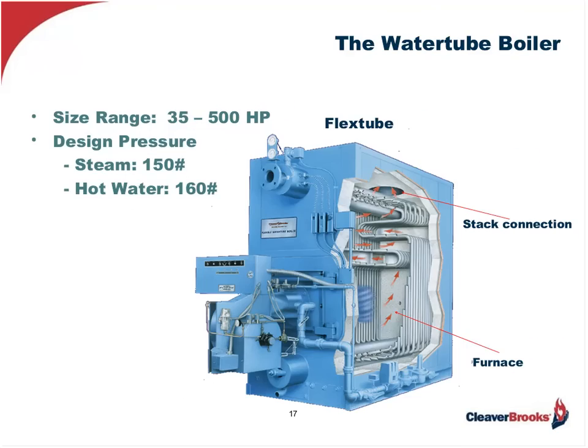The very popular Flextube boiler uses serpentine tubes connected to upper and lower headers, forming the various gas passes required to absorb heat. In this design the hot gases make five distinct passes, including the first pass in the furnace, before exiting to the stack. This boiler was originally designed primarily for hot water comfort heating as it was much more resilient to thermal shock, but was also found to be an excellent steam boiler for some process applications. It also has a distinct feature in that it can be readily field-erected because the tubes are swedged into the respective headers, not requiring any welding.